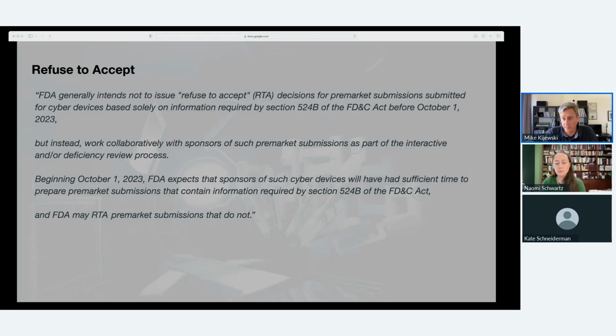Yeah. One related topic that I've seen come up between you and some of your clients, there are cases where the design attributes of a medical device make it very difficult or impossible to achieve some otherwise reasonable security goal, right? So for example, you shouldn't in general send data in plain text from place to place, but maybe you are a startup medical device manufacturer, you're building an implantable device that has an extremely low power processor, and you can't do cryptography on the data as it travels between the implant and some programmer device. In the past, we've seen device manufacturers just sort of not really talk about the fact that they're sending data in plain text and hope that it gets through the FDA.